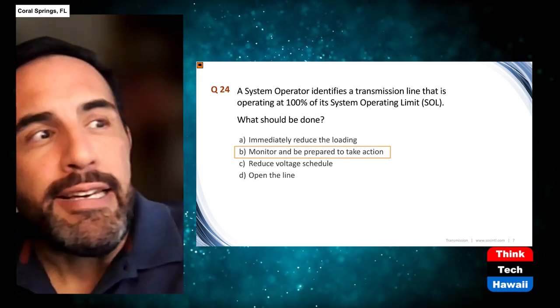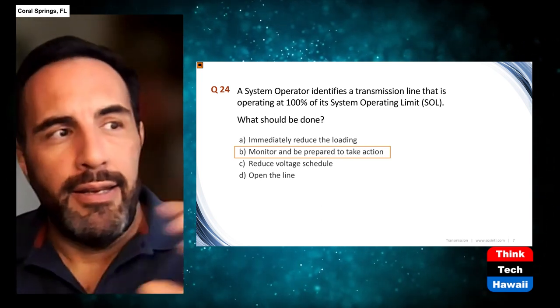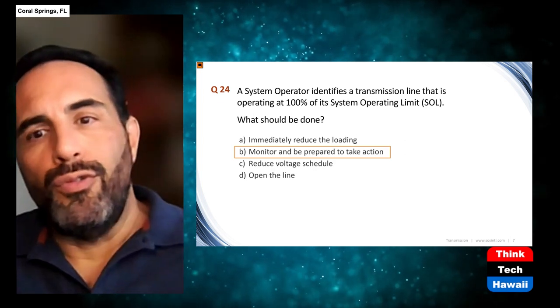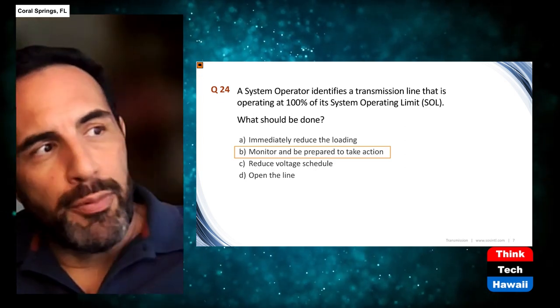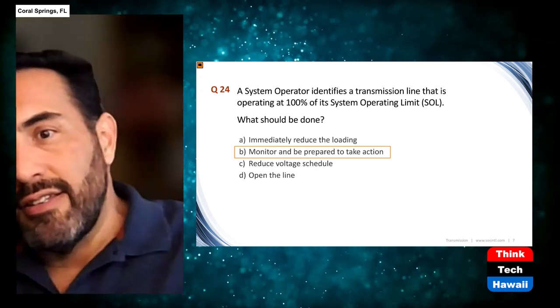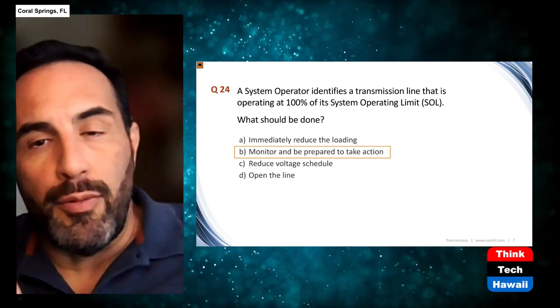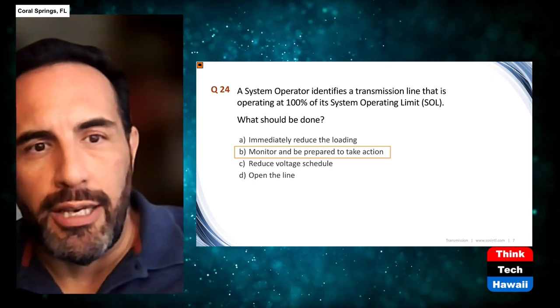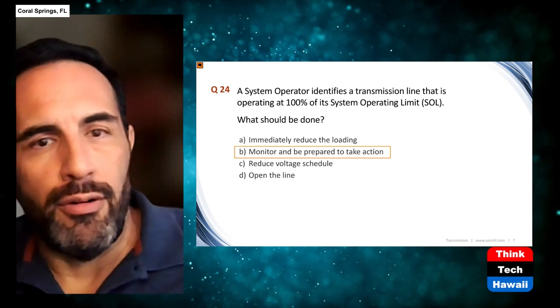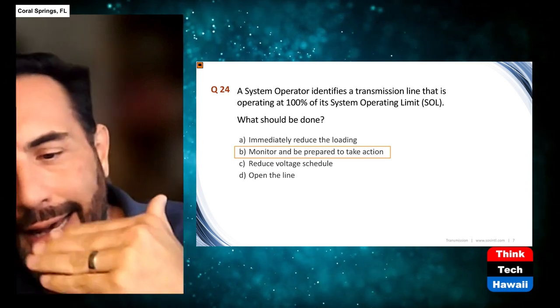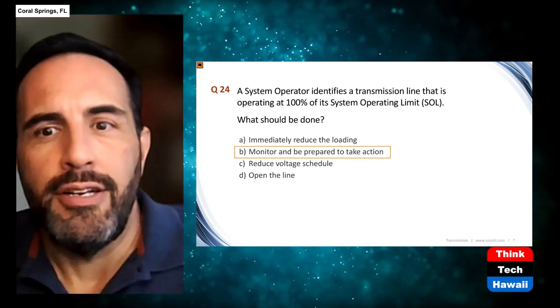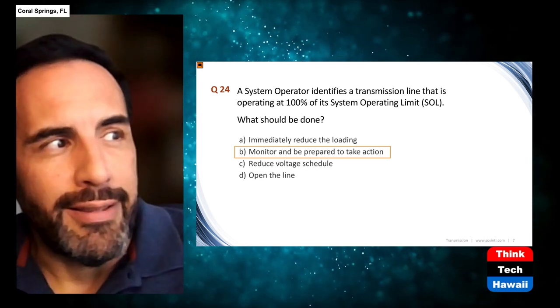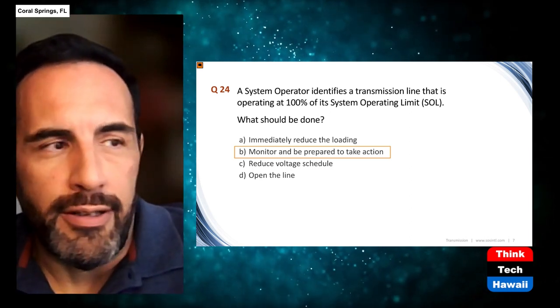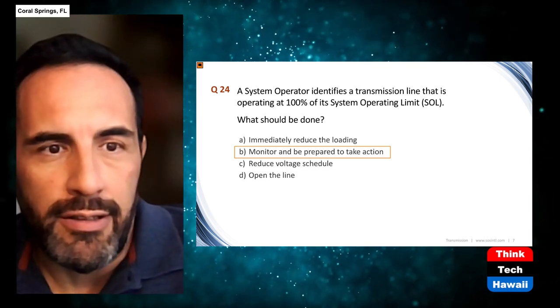If you have a pre-contingency event, meaning that if you lose a certain element, you'll be at 100% or more, then that's a pre-contingency event. It hasn't happened yet, but you need to be really ready to take action right away if it happens. In this case, something may have already happened where you're at 100%, right on that edge, and you haven't gone over that yet. If you were at 101%, then you would actually need to take some action at that point.